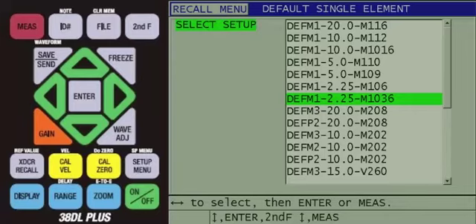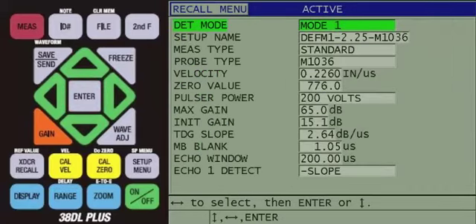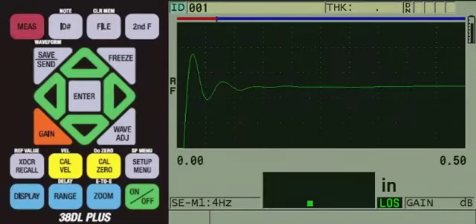Press the down arrow to highlight DEF M1-2.25-M1036. At this point, you can press the red Measure key to recall the setup or press the Enter key to see the parameters within the setup. If you press Enter, press the red Measure key next in order to recall the setup and return to the measurement screen. The default setup we recalled has a default sound velocity for stainless steel, so we need to change it to something closer to rubber.